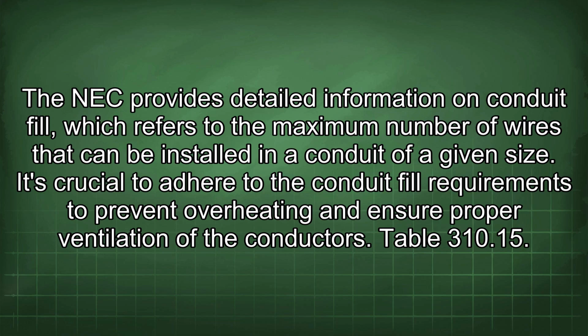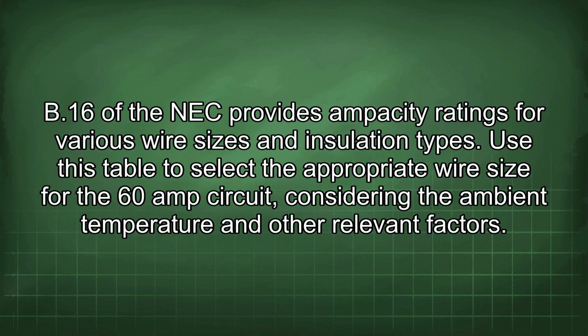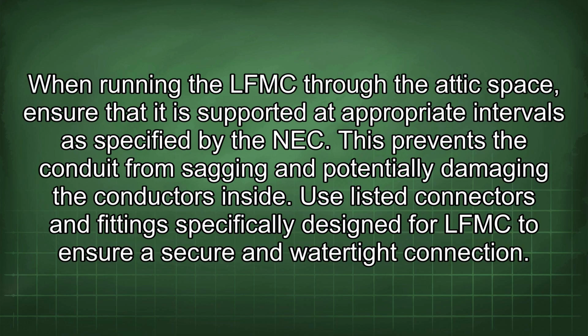It's crucial to adhere to the conduit fill requirements to prevent overheating and ensure proper ventilation of the conductors. Table 310.15(B)(16) of the NEC provides ampacity ratings for various wire sizes and insulation types. Use this table to select the appropriate wire size for the 60-amp circuit, considering the ambient temperature and other relevant factors.